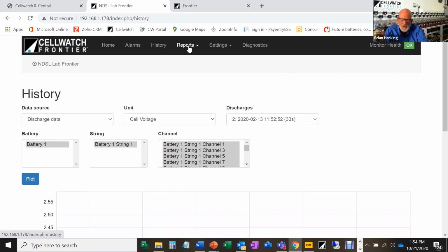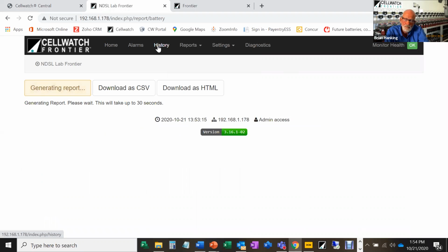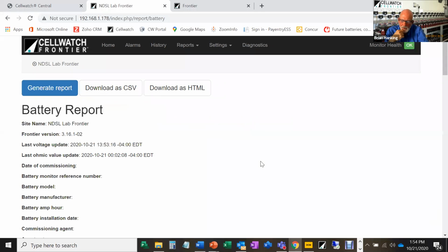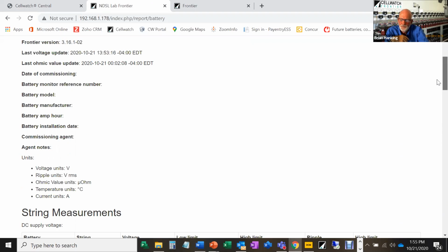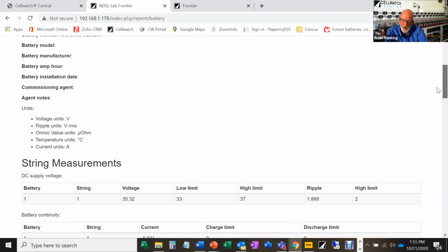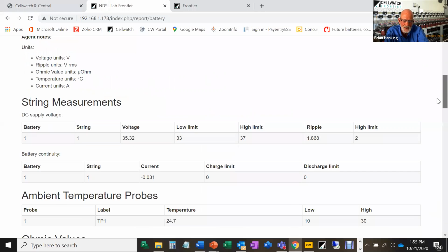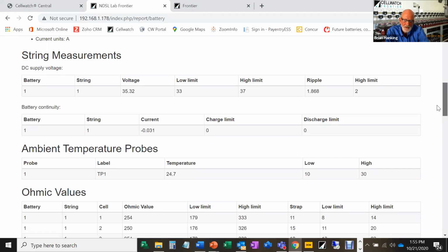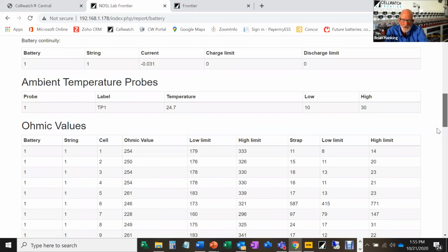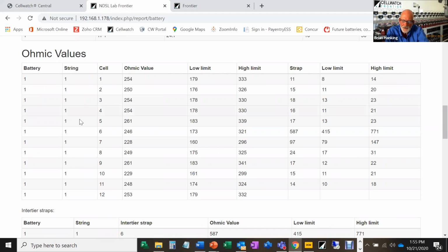So reports, of course, you can get battery reports as well. And again, this is from a system that might be down the road, or in Singapore, or in Northern California. We're generating a report right now, and you'll see we have a lot of information at the top about the system, much of which is entered at the start. Then we have a full gamut of string measurements, temperature probe measurements, all the individual ohmic values, and what the limits are, which can be set individually for individual jars.